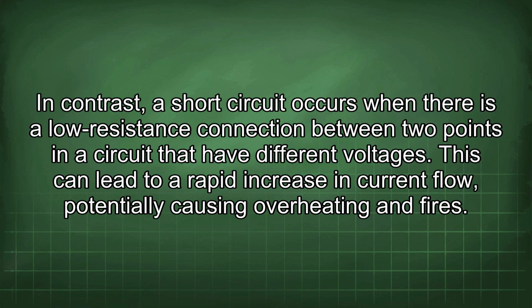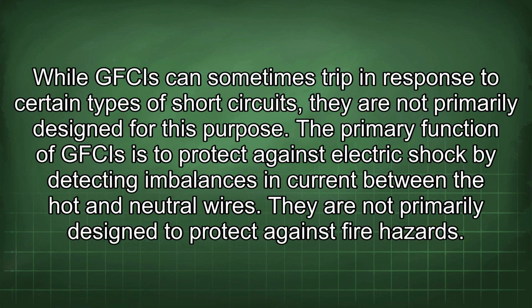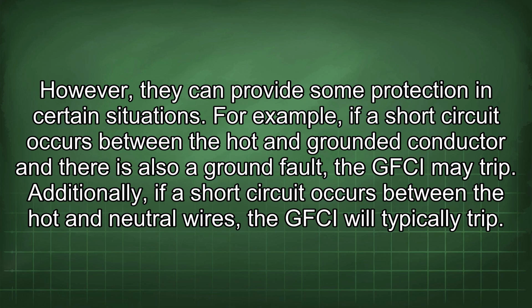This can lead to a rapid increase in current flow, potentially causing overheating and fires. While GFCIs can sometimes trip in response to certain types of short circuits, they are not primarily designed for this purpose. The primary function of GFCIs is to protect against electric shock by detecting imbalances in current between the hot and neutral wires. They are not primarily designed to protect against fire hazards. However, they can provide some protection in certain situations.